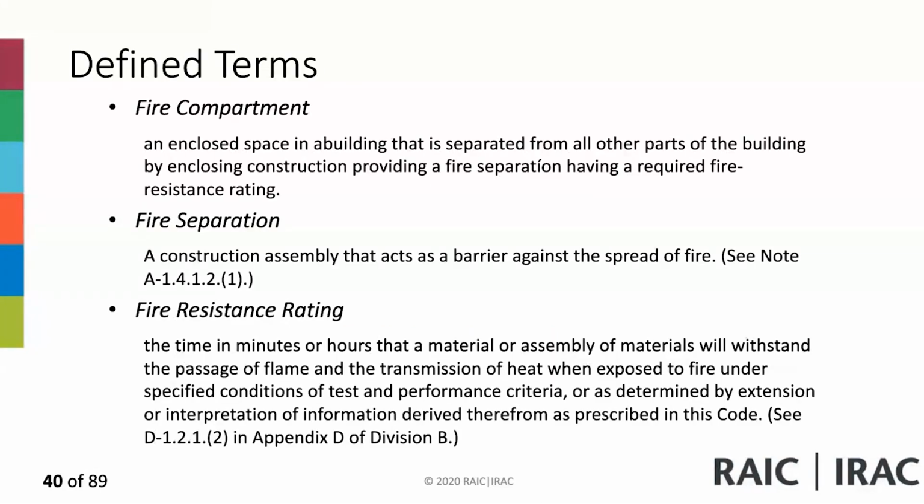So fire separation, fire resistance rating. The fire resistance rating is a critical element for types of construction. Each building is going to be built to a certain type of rating for its floors and structural members. It is the time in minutes or hours that a material or assembly of materials will withstand the passage of flame and the transmission of heat when exposed to fire under specified conditions of test and performance criteria.